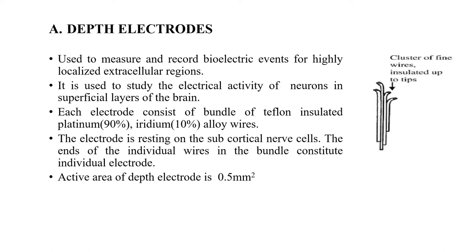The active area — that is, the area that can be covered by the depth electrode — is about 0.5 mm².